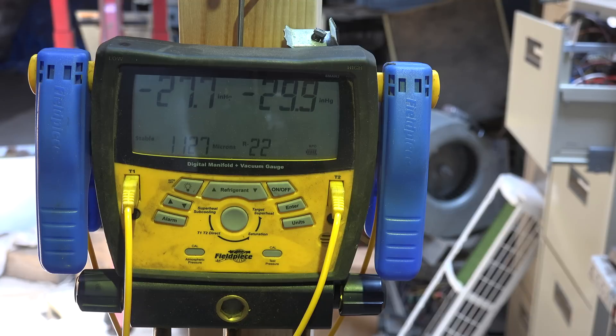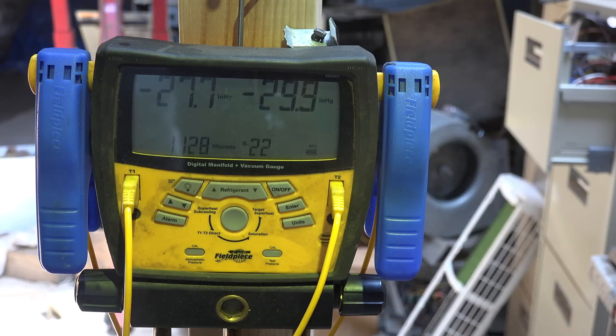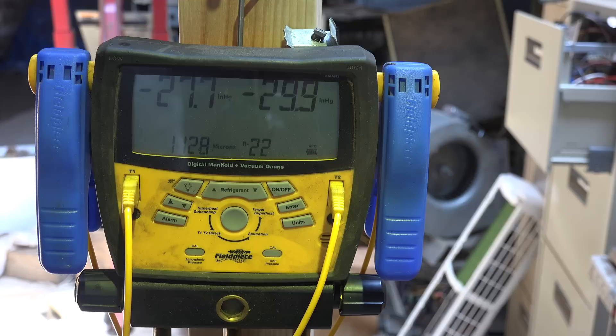That's why we come to that 1000 to 1500 microns. If it stops in that area, don't look for a leak. That is moisture in the system.